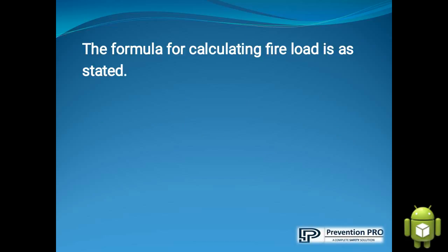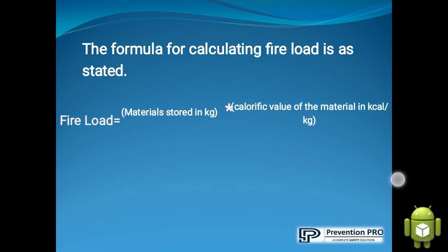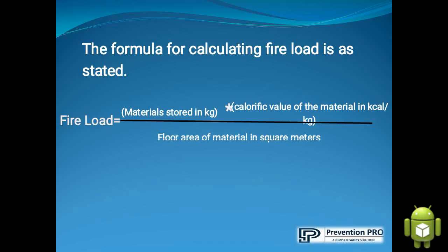The formula for calculating fire load is as stated. Fire load is equal to material stored in kilogram multiplied by calorific value of the material in kilocalories per kg, the whole thing divided by floor area of the material in square meters.